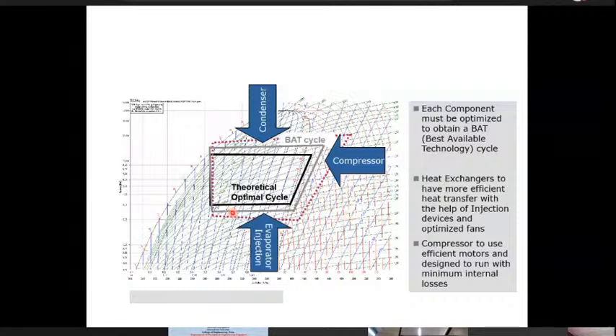Then we can look for compression technology which more closely resembles the isentropic process. If the compressor was redesigned with an eye on efficiency, we could look at better lubricants, closer tolerances, different material wear characteristics, and valves having a lower pressure drop. We could even look at compression technology which changes. Instead of using a reciprocating compressor, can we use a scroll compressor? Is a rotary compressor better than the reciprocating compressor? Those are the situations that will come to mind when we are looking at compression technology. And in case of large systems, do we go to a screw compressor or do we go to a centrifugal compressor?